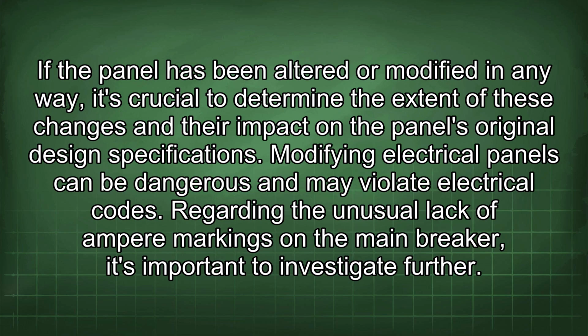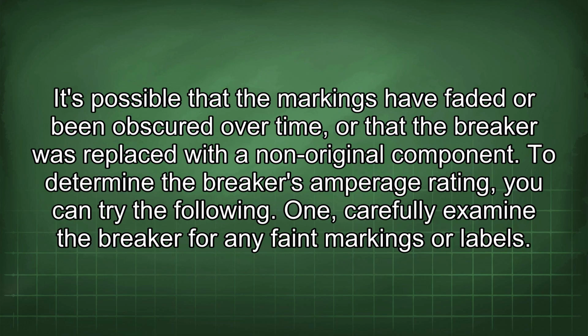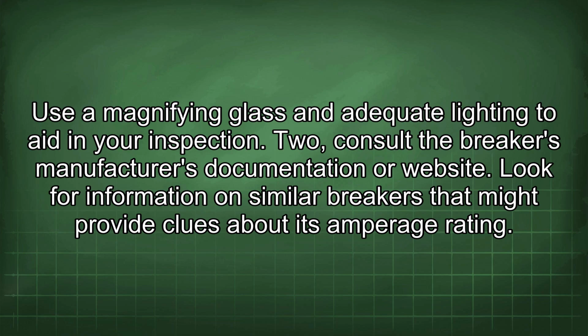Regarding the unusual lack of ampere markings on the main breaker, it's important to investigate further. It's possible that the markings have faded or been obscured over time, or that the breaker was replaced with a non-original component. To determine the breaker's amperage rating, you can try the following. 1. Carefully examine the breaker for any faint markings or labels. Use a magnifying glass and adequate lighting to aid in your inspection. 2. Consult the breaker's manufacturer's documentation or website. Look for information on similar breakers that might provide clues about its amperage rating.